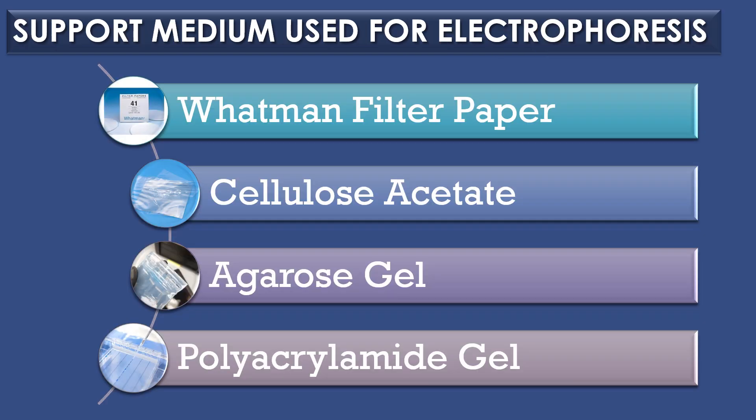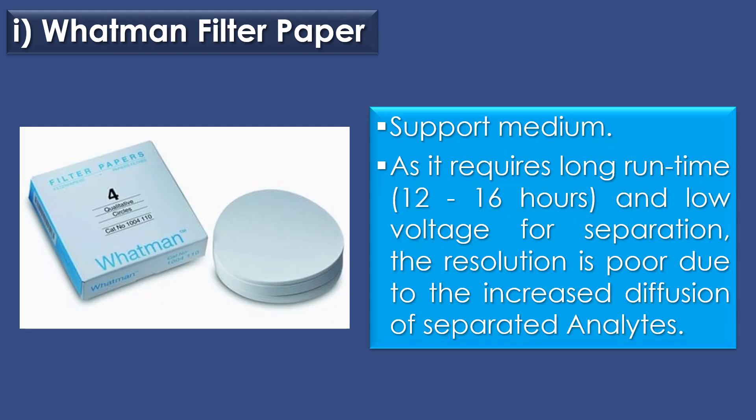Support medium used for electrophoresis: four support media are used for electrophoresis — Whatman filter paper, cellulose acetate, agarose gel, and polyacrylamide gel. The first support medium is Whatman filter paper. It requires a long running time of 12 to 16 hours and low voltage for separation. The resolution is poor due to the increased diffusion of separated analytes.